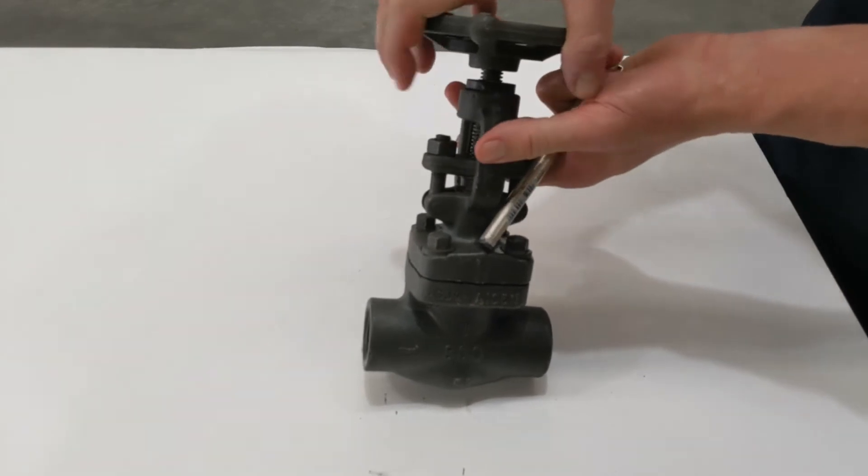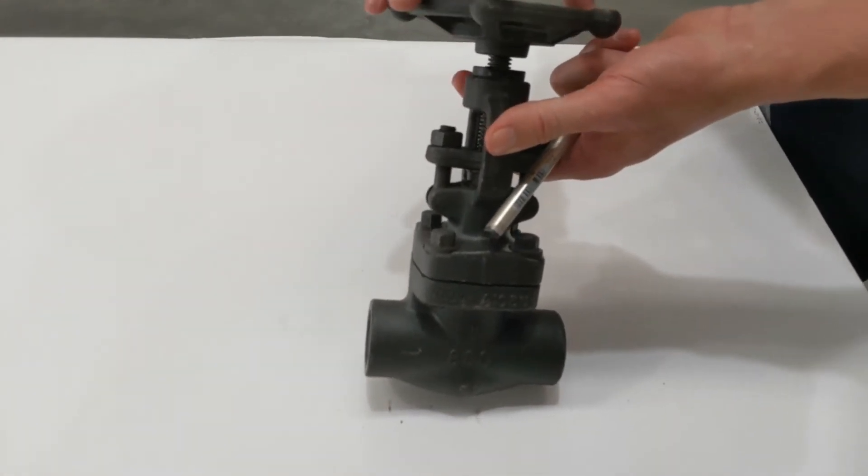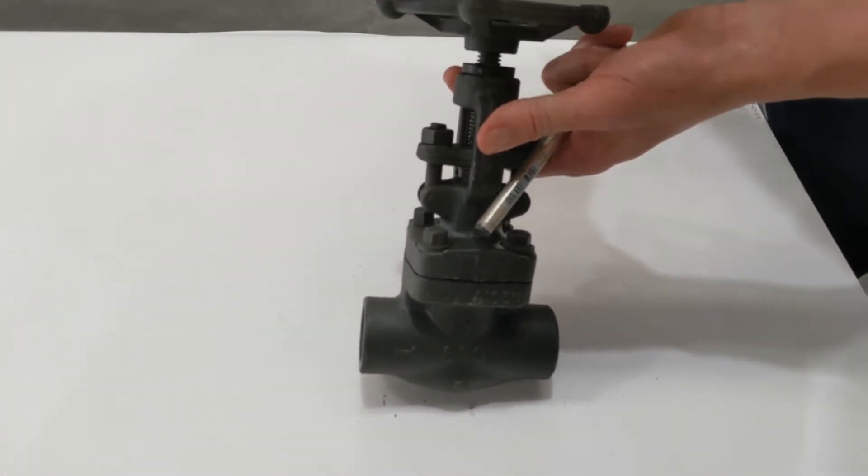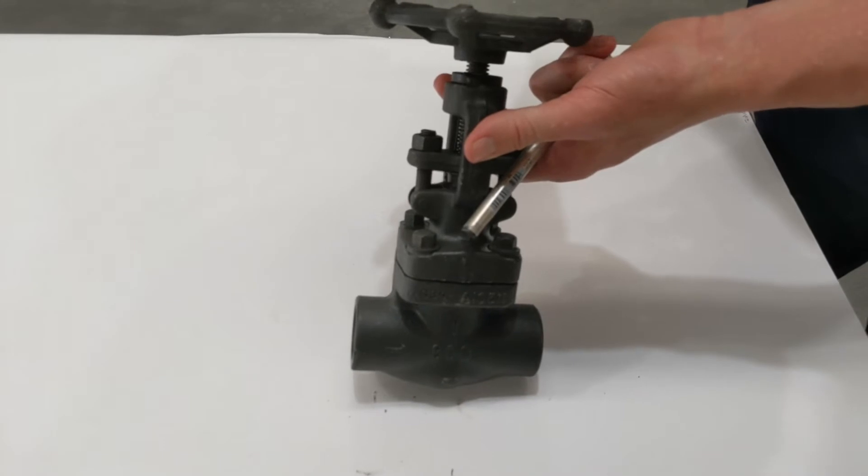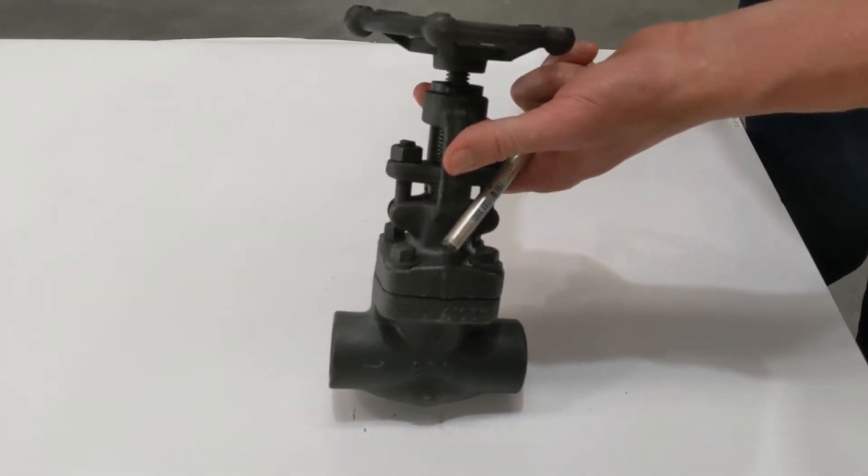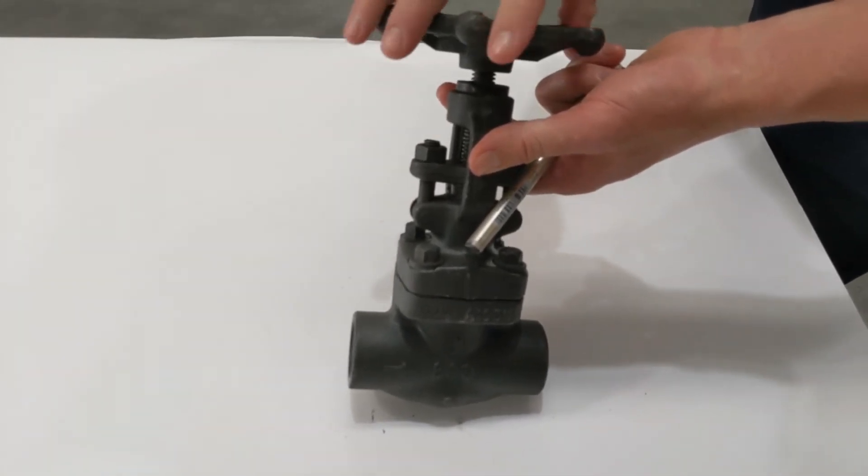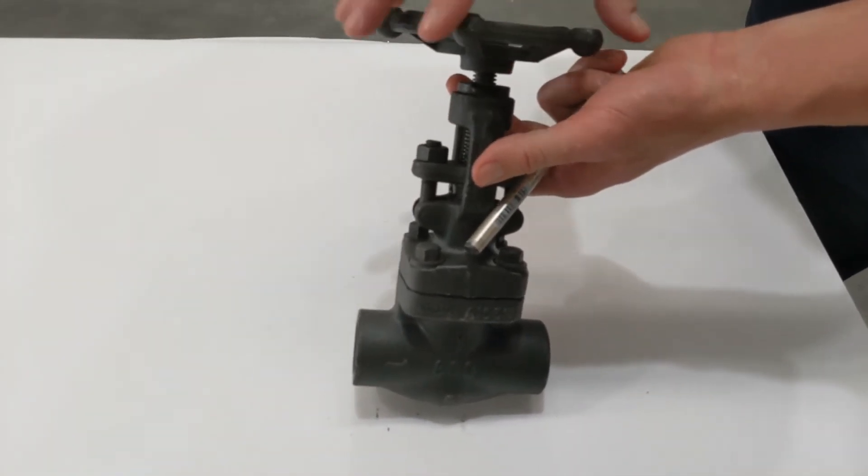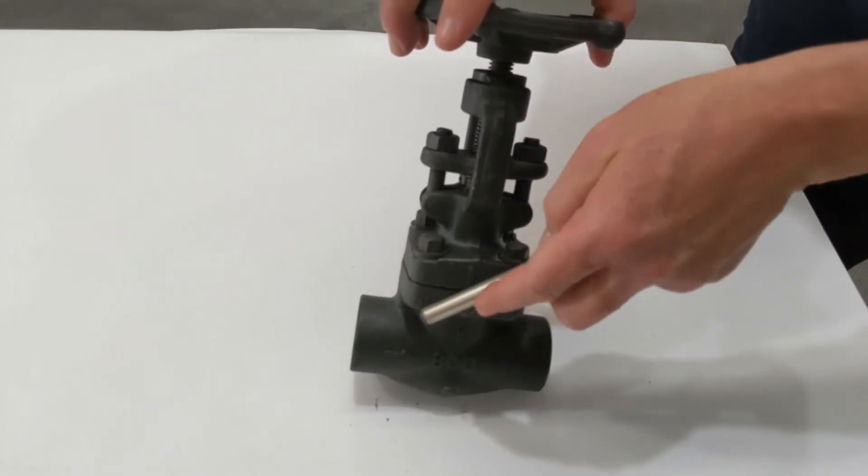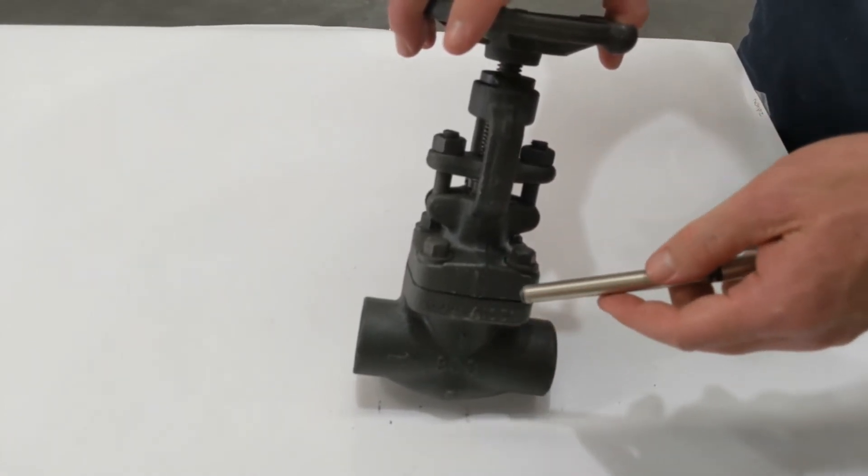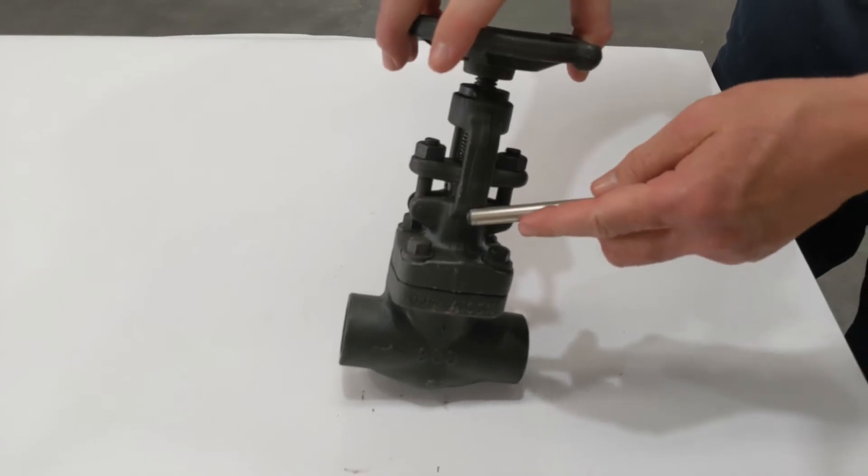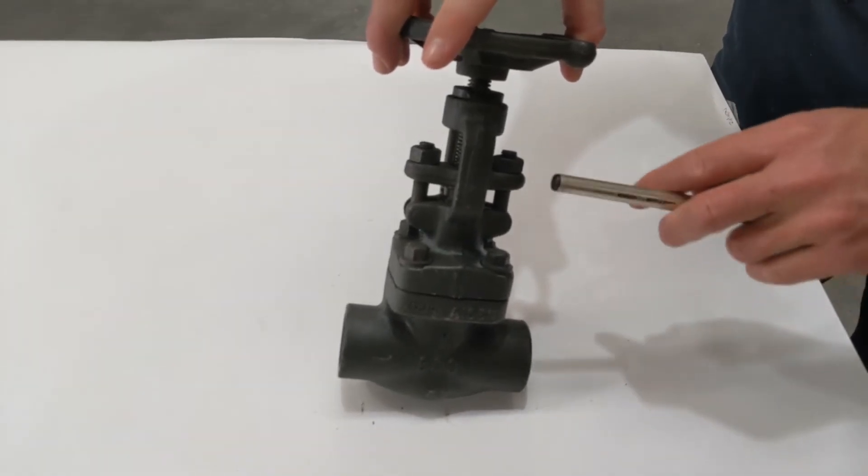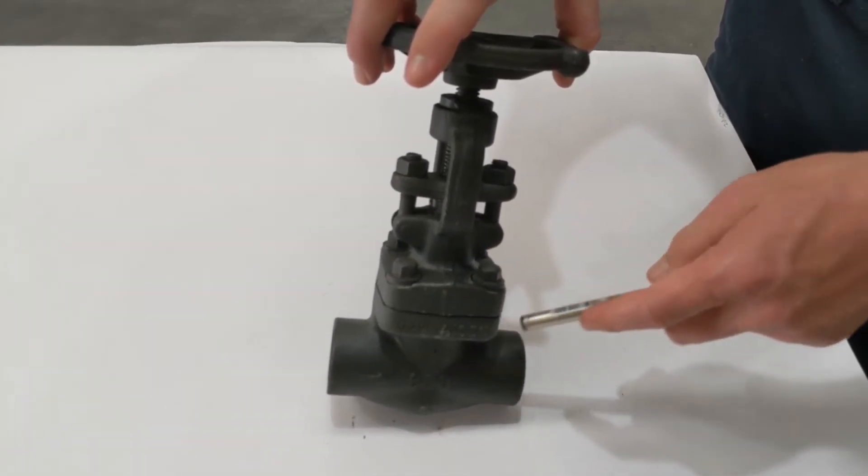A globe valve like this is quite good in steam applications or something where you need throttling or you need to open and bring the line up to pressure slowly. As you open it, because it's got a globe, it only slowly lets some of the flow through until it's right up into the top of its cavity, and likewise when you're closing it, it will cut the flow down.